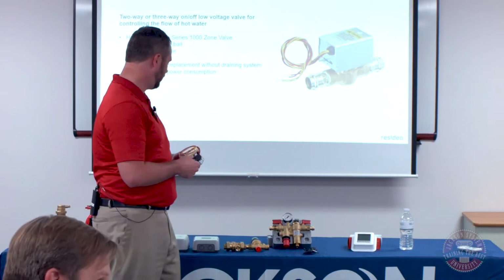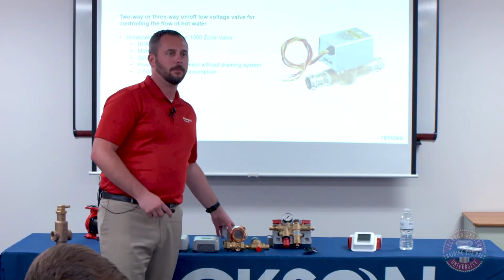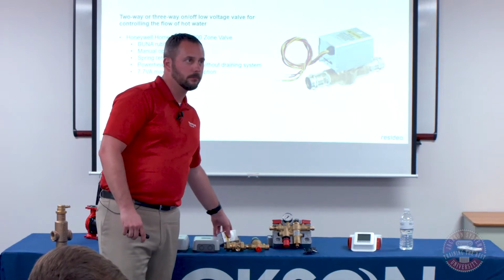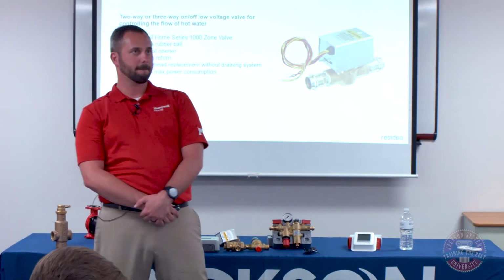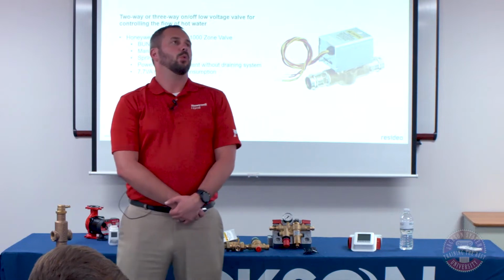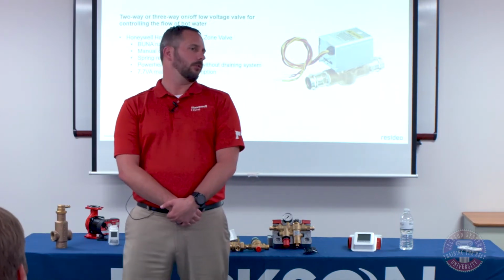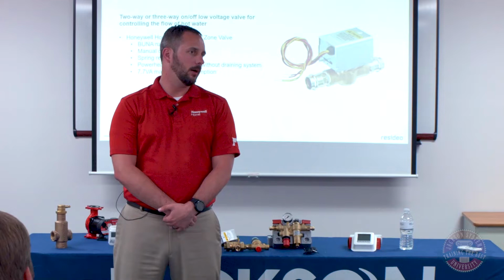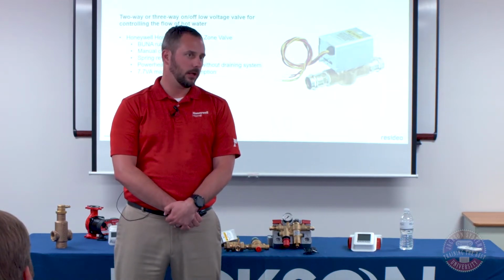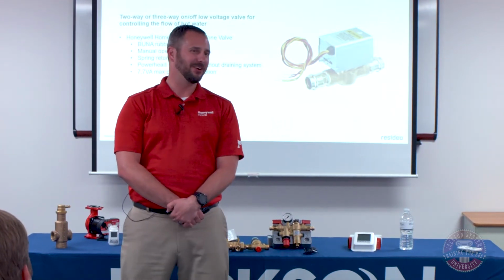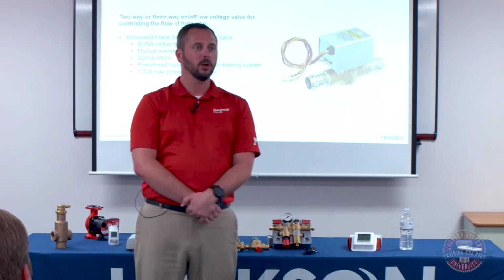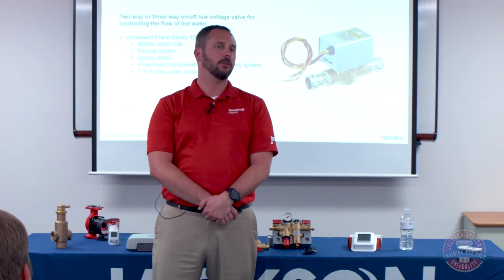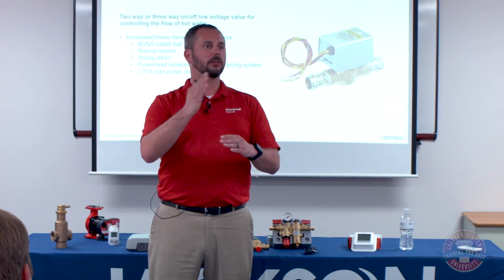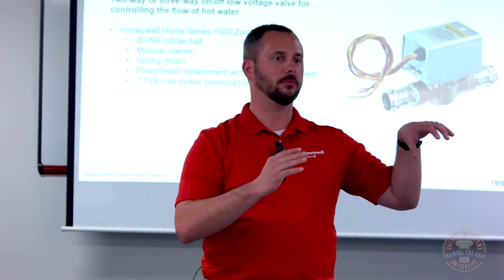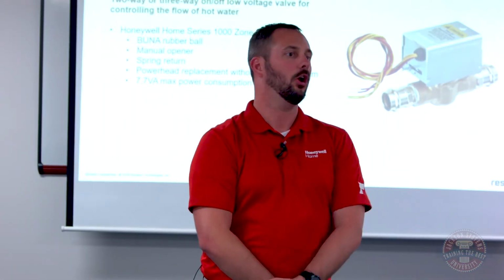Two more questions. Leon asks, do you offer a 3-way mixing valve in 1/2 inch for hot-cold water coils? 3-way mixing and diverting are a little bit different. We do have that product offering. It's in that same series of valve I was talking about, where it's power open, power closed. Because in a mixing valve, you have to give it a certain level of operation, so you typically have some kind of control that's sensing it and driving it somewhere. We do have some products that can handle that.